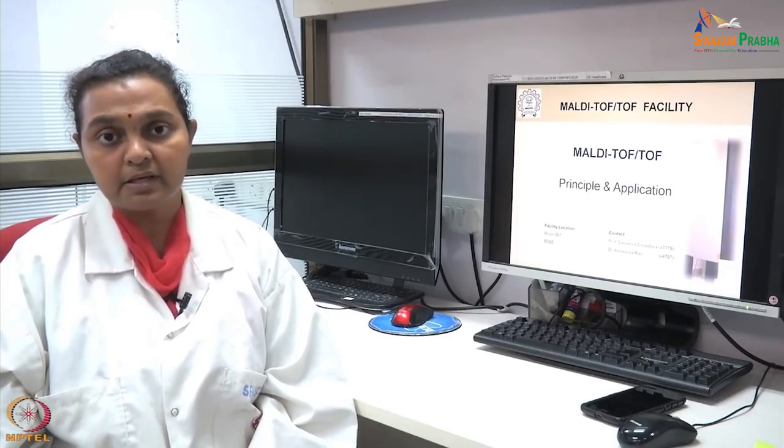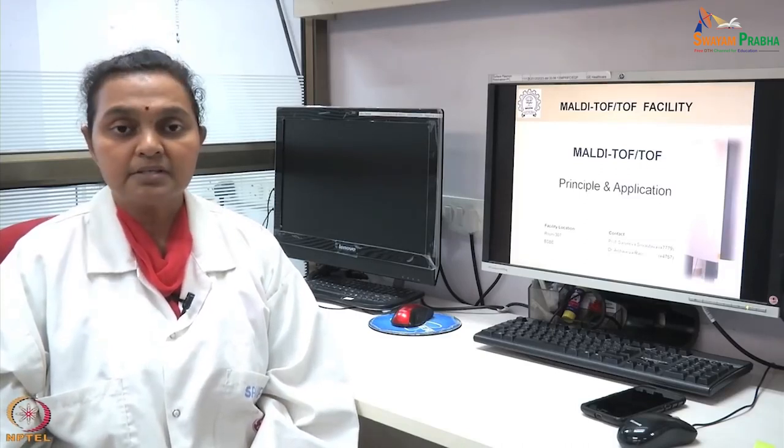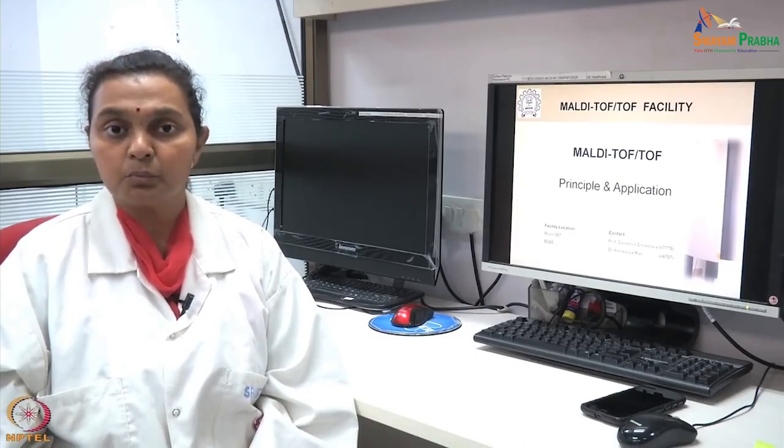It is very important to understand the term matrix. The matrix is a chemical compound mixed with the sample—chemical compounds capable of absorbing energy from the laser beam and transferring it to the sample so that the sample gets ionized. The matrices are chosen based on the type of sample to be analyzed. They help the sample ionize with minimal fragmentation, enabling analysis of very fragile samples like DNA, proteins, sugars, and polymers.